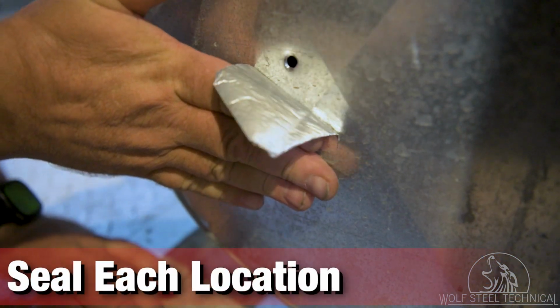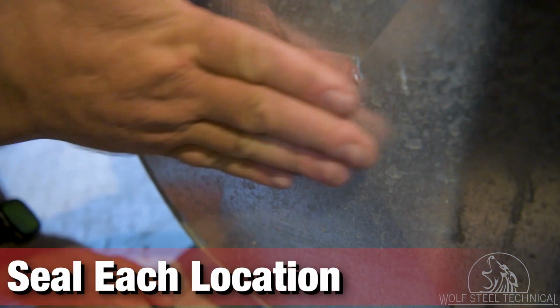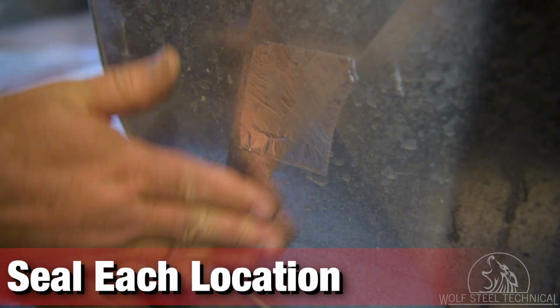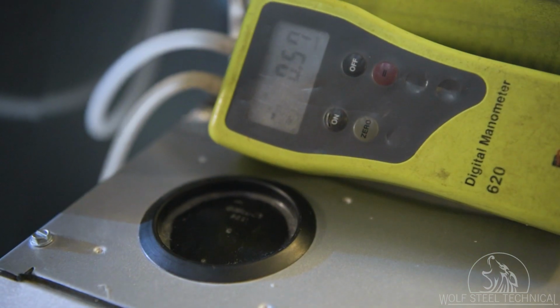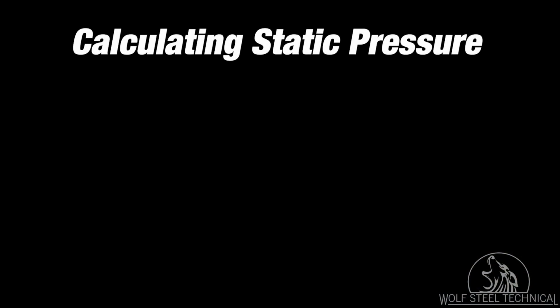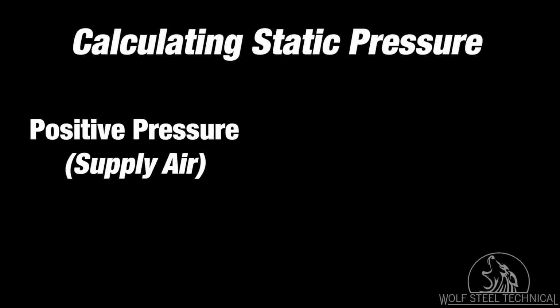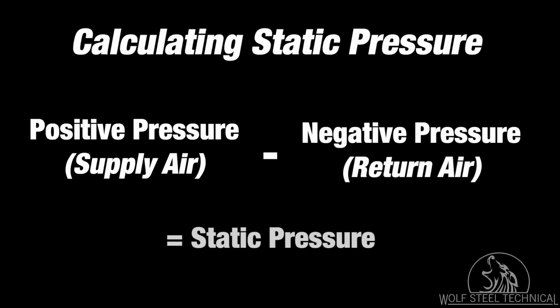Ensure to seal each location with foil tape after you have measured the pressure to keep the system as airtight as possible. If you are not using a digital manometer, you can calculate the static pressure by identifying the positive pressure reading measured on the supply side and subtracting your negative pressure reading measured on the return air side.